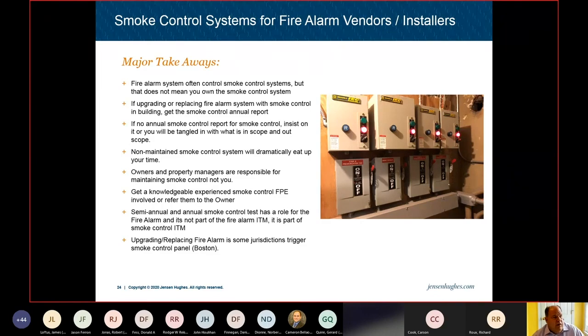If you're upgrading or replacing the fire alarm system with the smoke control system in the building, get the smoke control system annual report. It's going to save you a lot of headaches to make sure that they've done it. What you'll find is they most likely haven't done it. So if there is no smoke control report for that building, insist on it, or you'll be tangled in what is in scope and what's out of scope, and you're just going to get sucked in. There are interfaces to that, but especially for these older smoke control systems that have not been maintained, it takes a lot of time and effort, including getting service companies involved, including fire alarm service companies, to detangle all that stuff. So you're testing things and fans aren't turning on or actuators aren't actuating because this stuff has been sitting there sometimes for decades not being used.